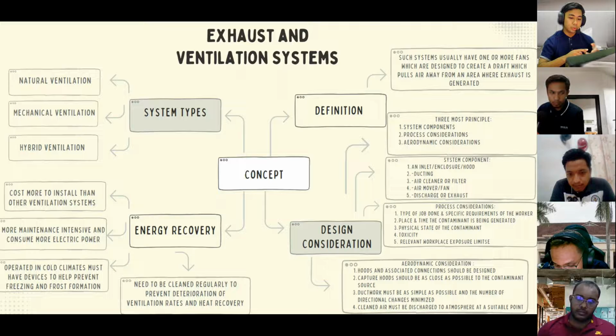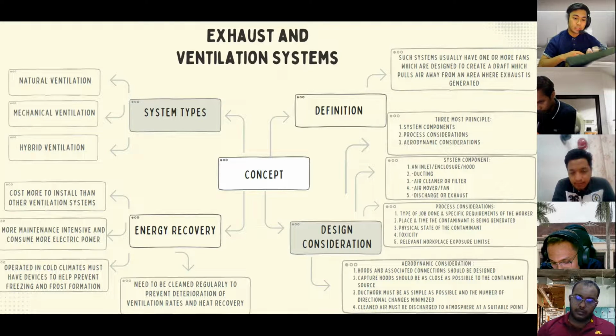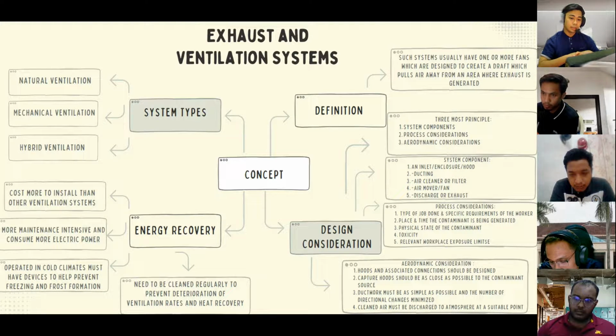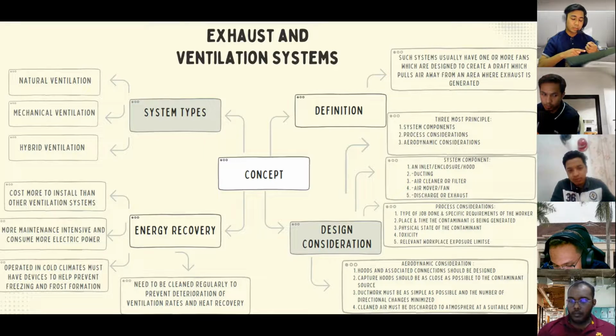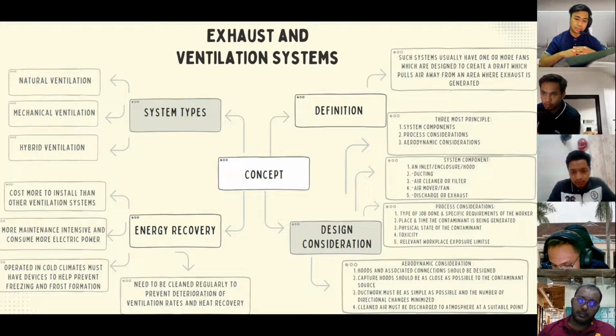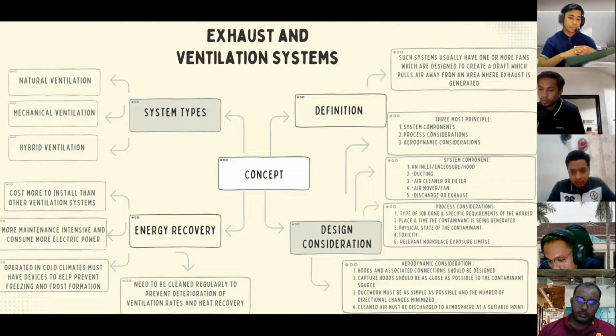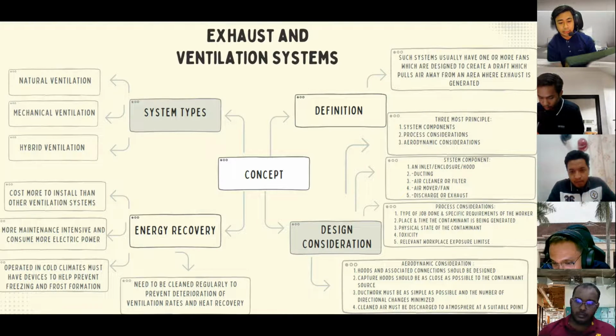Mechanical ventilation systems usually have one or more fans which are designed to create a draft which pulls air away from an area where exhaust is generated. Both new and existing buildings require mechanical ventilation to maintain indoor air quality. Consequently, there are four mechanical ventilation systems to choose from, which are exhaust, supply, balance, and energy recovery. The third type of general ventilation is hybrid ventilation. This ventilation is a mix of natural and mechanical ventilation.